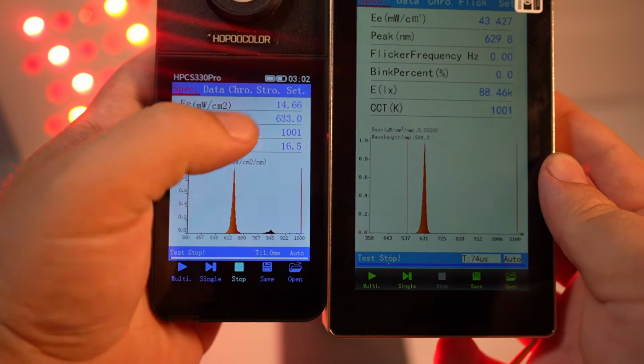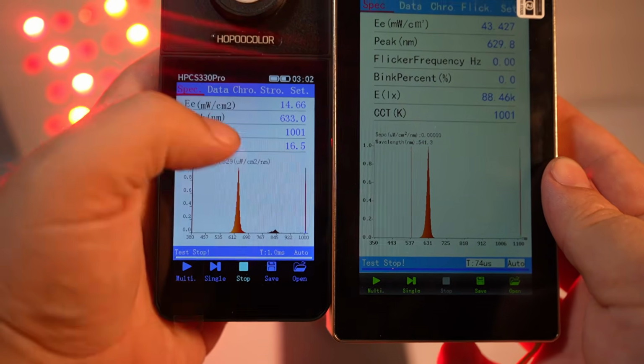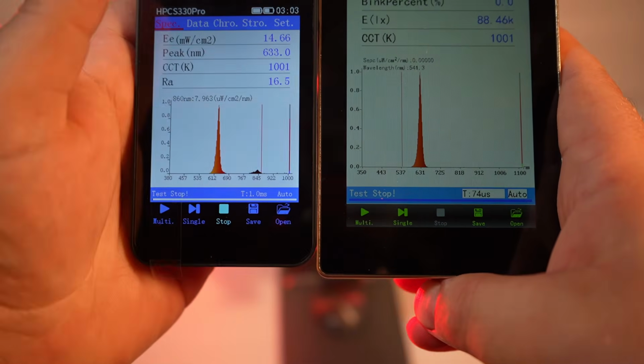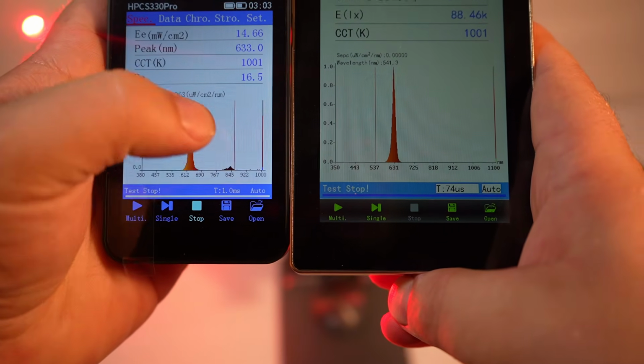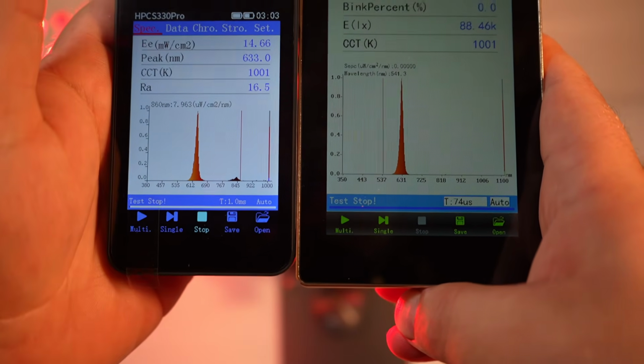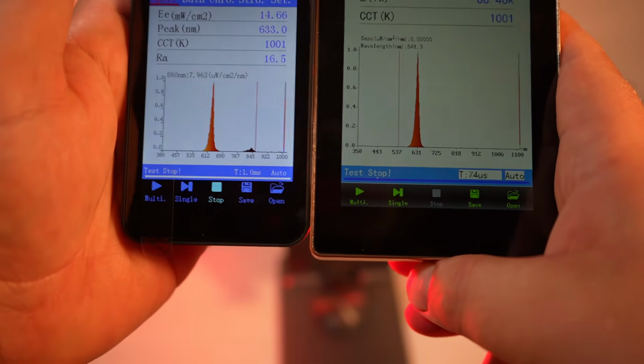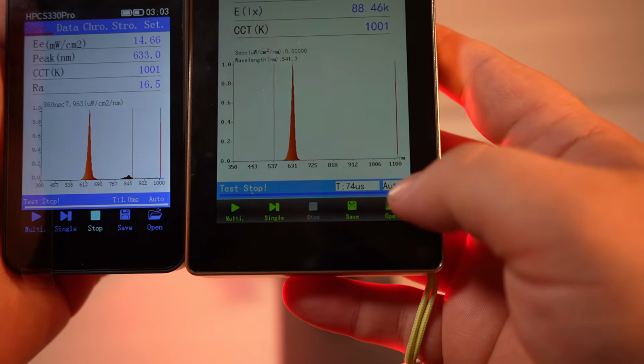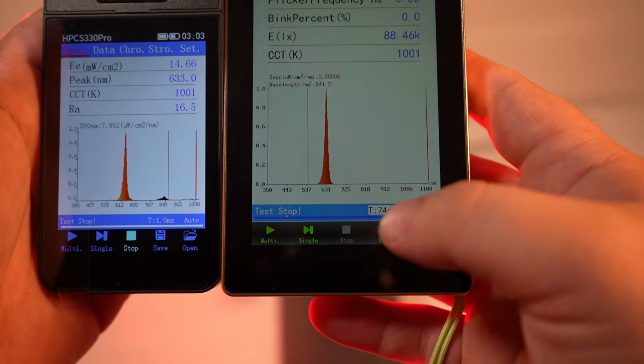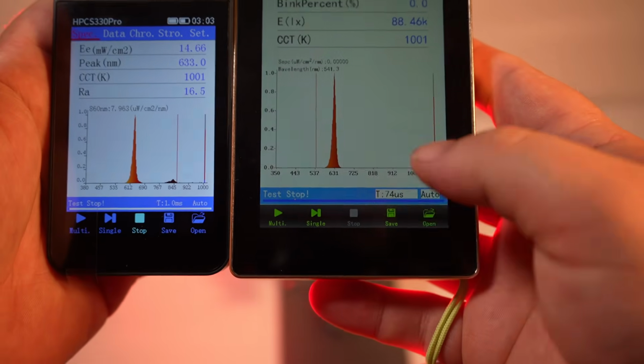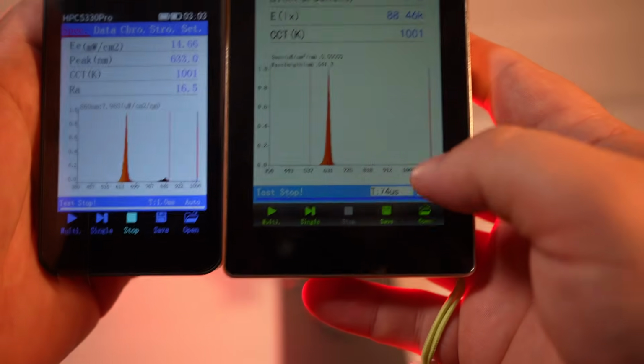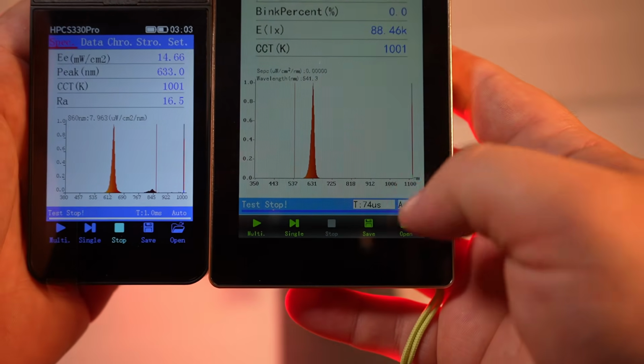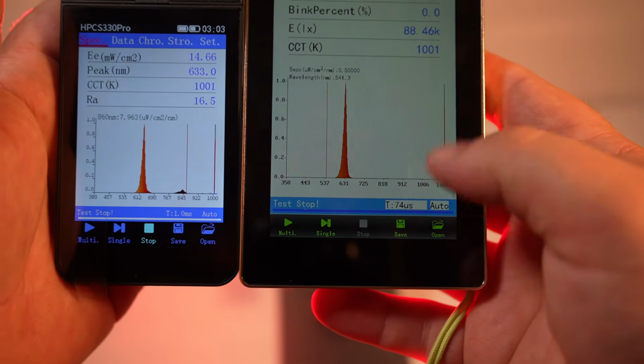It does a spectrometer and the intensity, so that's why it's called a spectroradiometer. But there's one other limitation: the cheap one only goes up to 1,000 nanometers, which again is very good. It should cover the vast majority of devices on the market, but you can get the more expensive one up to 1,100 nanometers. So if you really need to measure those 1050s, 1060s, 1070s, then you'd have to pay a lot more if you want that extra range.